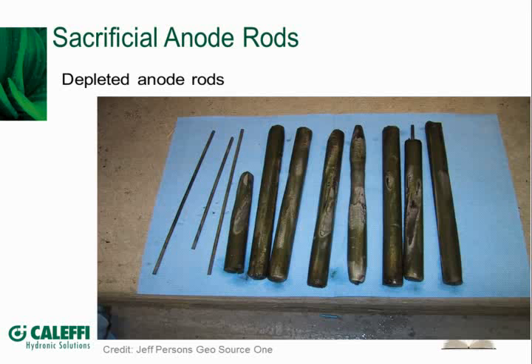But it was a matter of having an aggressive water supply, a very soft, hot water, that, shall we say, can dissolve a metal. Let's see, the solution rate doubles for every 10-degree increase in temperature. So if you start out with 50-degree water and you increase it to 120 degrees, you've increased the solubility of metals in that system many, many times over by the time you get it to 120 degrees. And if you've got a little pump there that's running 24/7, that just accelerates the problem.